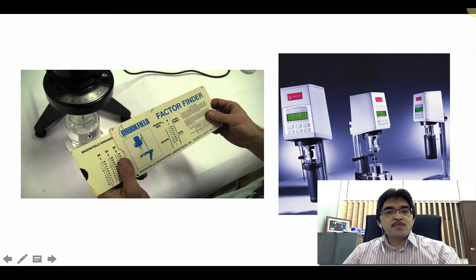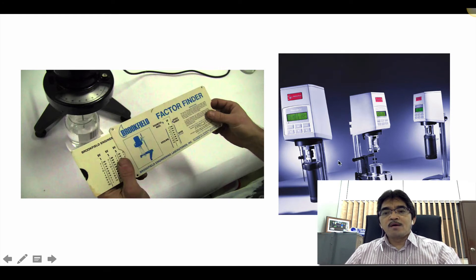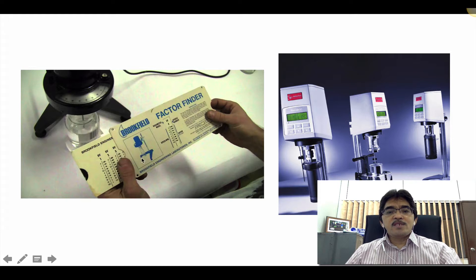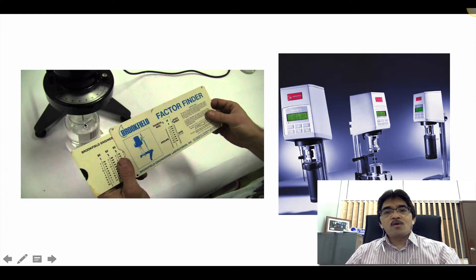We can measure the viscosity and express it in centipoise or pascal second. Or we can use a rheometer to determine the whole flow curve at different shear rates and shear stress, and plot the flow curve easily using a rheometer. Using this kind of instrument, we can choose to measure the viscosity at one constant shear rate, or we can also choose to measure the viscosity over a range of shear rate, for example, from 0 to 1,000 or even 10,000 reciprocal seconds.